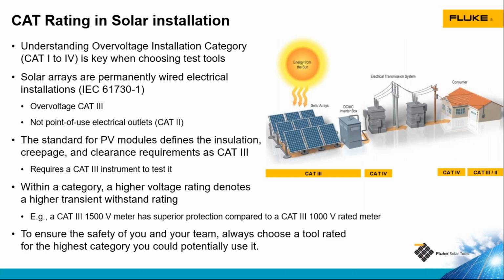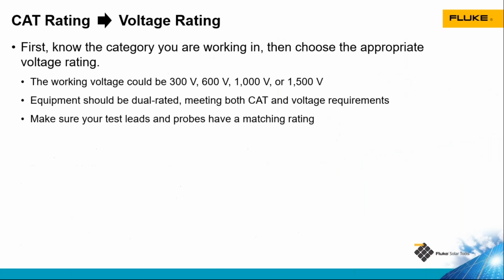These would be locations like our meter enclosures, service disconnects, certain parts of our load center, medium voltage transformers, and even on larger scale solar projects, it could be the entire AC output circuit from the inverter to the medium voltage transformer. We just need to make sure that we have a tool that's rated for the category in which we are working. And again, in solar, that's going to be category 3 for our array, category 4 for our point of interconnection close to the utility.